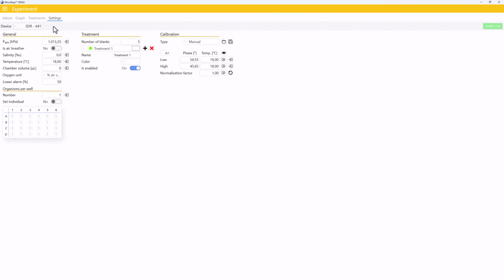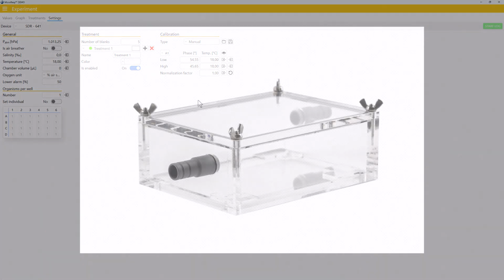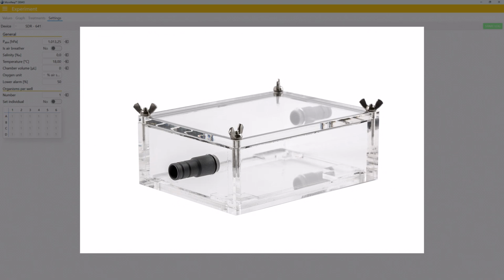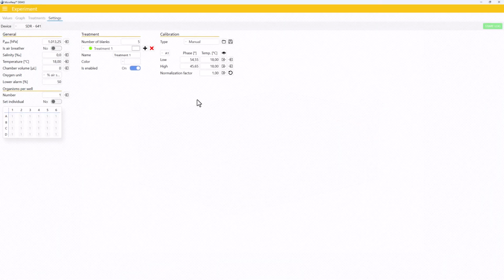If you're calibrating in air, simply follow the same steps as when calibrating in water. But instead of a 0% and 100% water sample, use just nitrogen gas for the 0% calibration and leave the sensor spots exposed to the ambient air for the 100% calibration. Remember to maintain the temperature of especially the nitrogen gas also within plus minus 1.5 degrees of your experimental temperature. The optional flow-through water bath can be useful since you can pass gas through the closed water bath to easily expose all of the sensor spots.